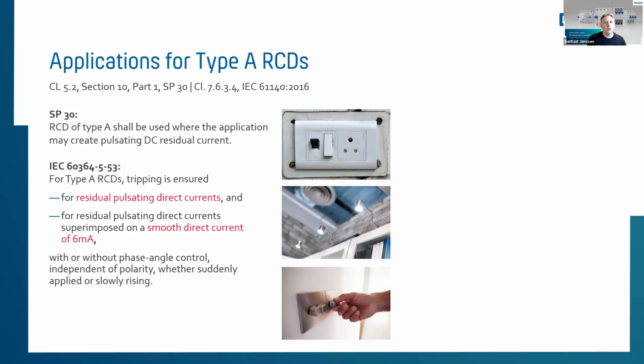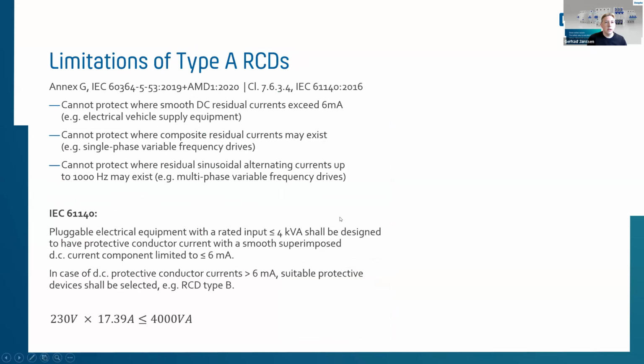So as per the electrical code, type A RCDs ensure tripping for residual pulsating DC currents and for residual pulsating DC currents superimposed on smooth direct DC currents, but only up to 6 milliamp of direct DC currents. If we exceed the 6 milliamp DC threshold, then the type A is meanwhile not in the range anymore. You will see it afterwards in some of the other slides. What are the limitations of type A RCDs? They are not able to protect where smooth DC residual currents exceed the 6 milliamp DC threshold.